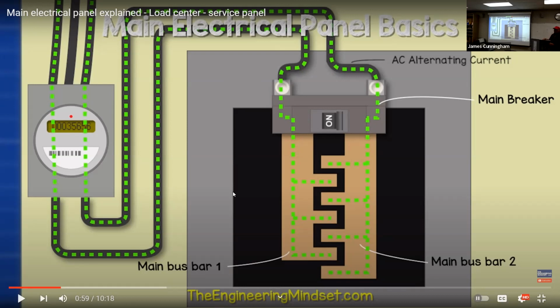Because what would happen if I just shut off one to my electric stove and then I went to work on it? You could get electrocuted because you didn't shut off the electricity to both sides of it. So when you have a 240 volt breaker, they have to be joined together. So you make sure that you've got both sides turned off when you're doing that.